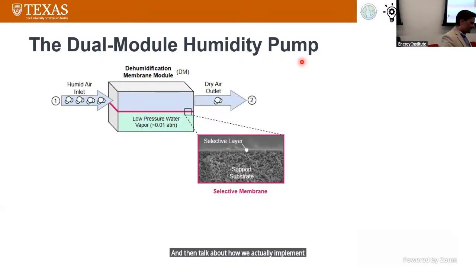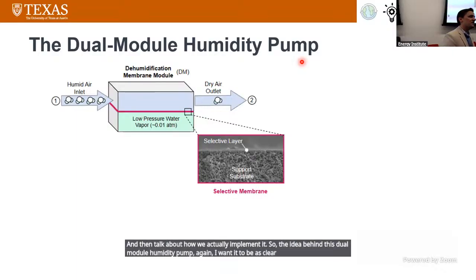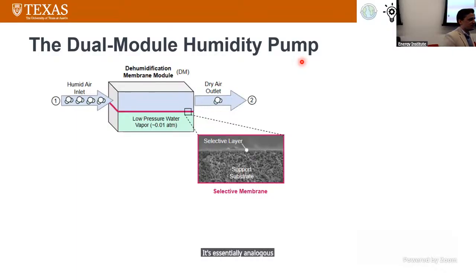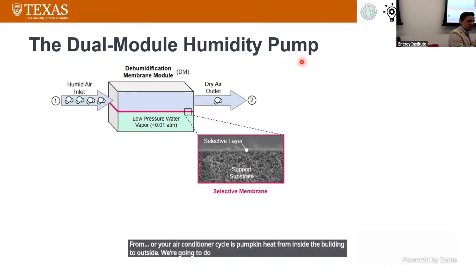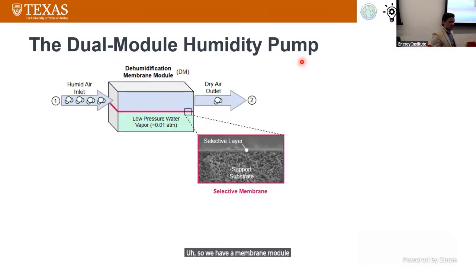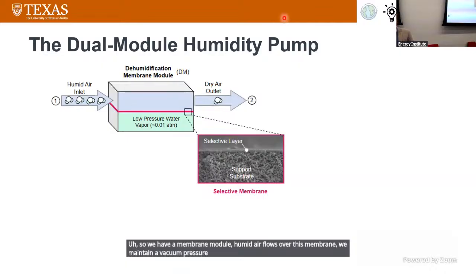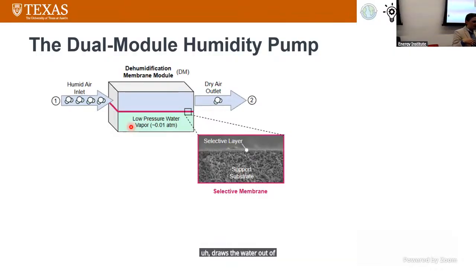The idea behind this dual module humidity pump—I want it to be clear that it's essentially analogous to a heat pump. A heat pump, or your air conditioner cycle, pumps heat from inside the building to outside. We're going to do the same now, but with water vapor instead of heat. So we have a membrane module. Humid air flows over this membrane, and we maintain a vacuum pressure on the bottom side of that membrane. The difference in water vapor partial pressure draws the water out of the air, and now we have to do something with it.